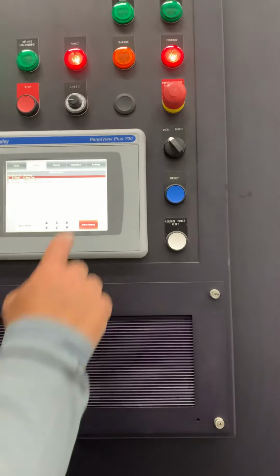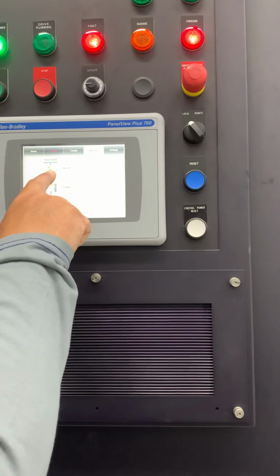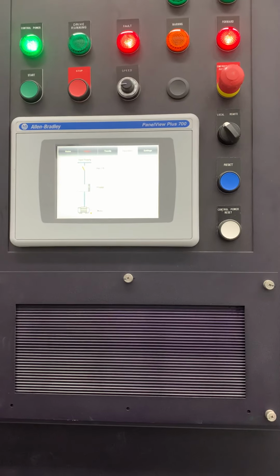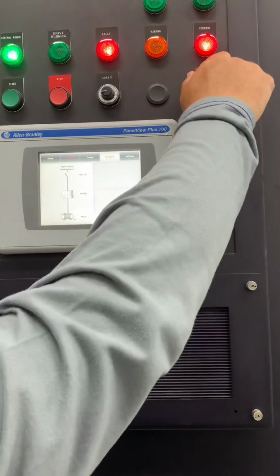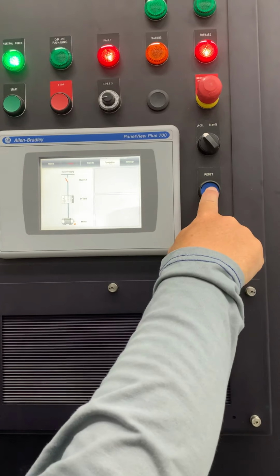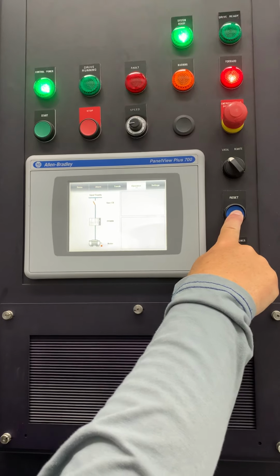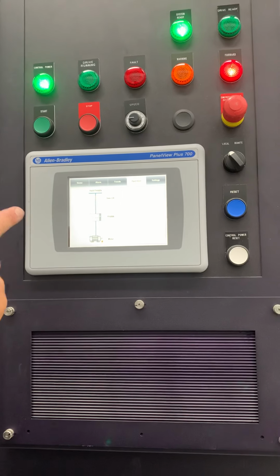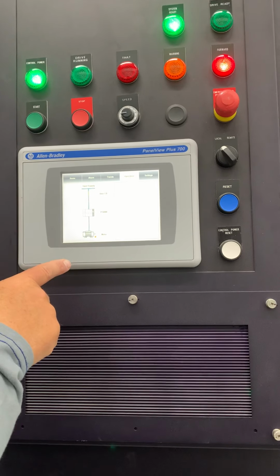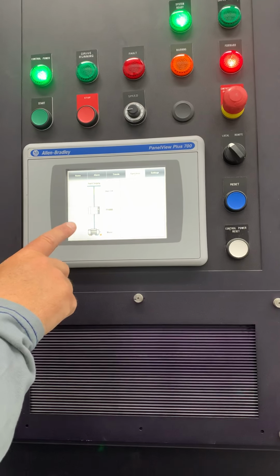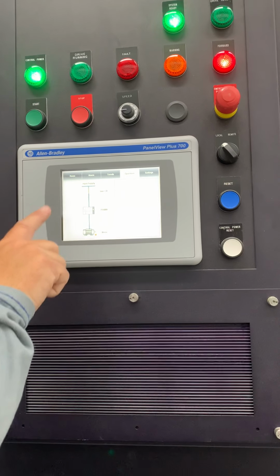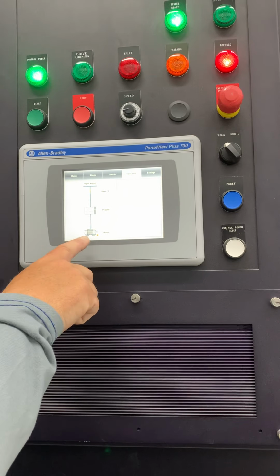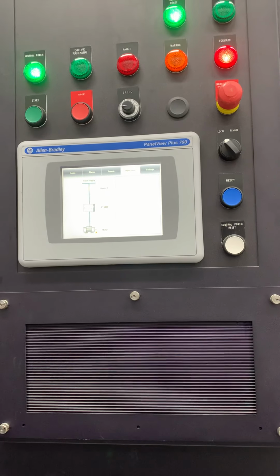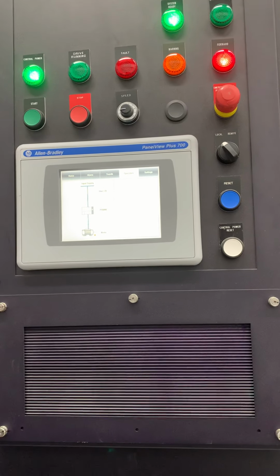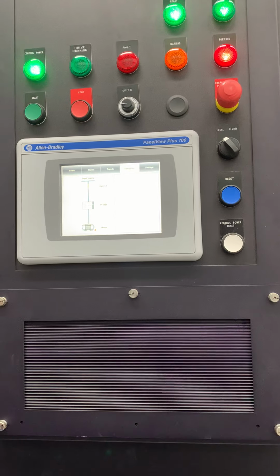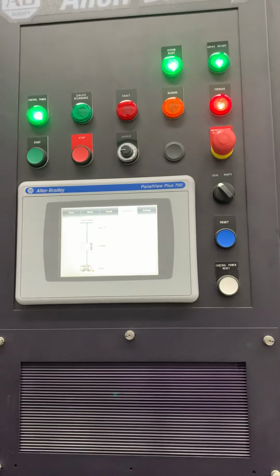Everything else, so you can go into operation and this will tell you that your input contactor is open. You got a graphic there. So you pull the e-stop, reset the alarm, then it'll go to green, show you the circuit breaker is closed, your drive will be ready when it comes up ready, and whenever you run the motor, then it'll turn green and all that stuff too. So just a simple graphic. It's just really noisy with the fan.